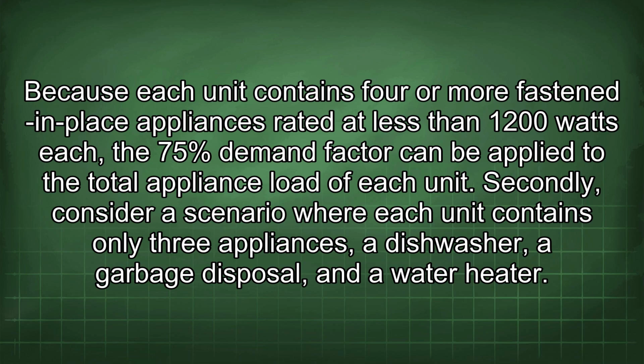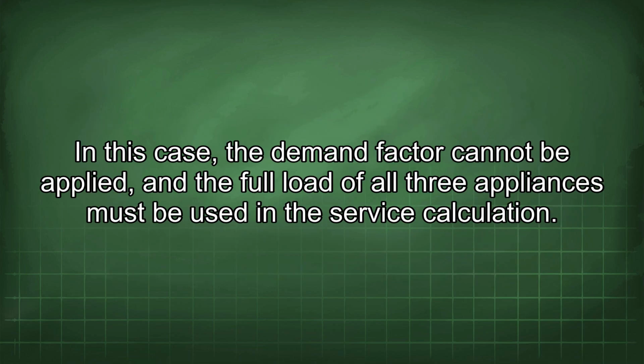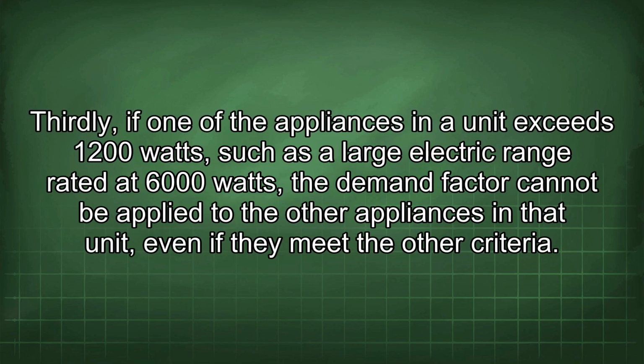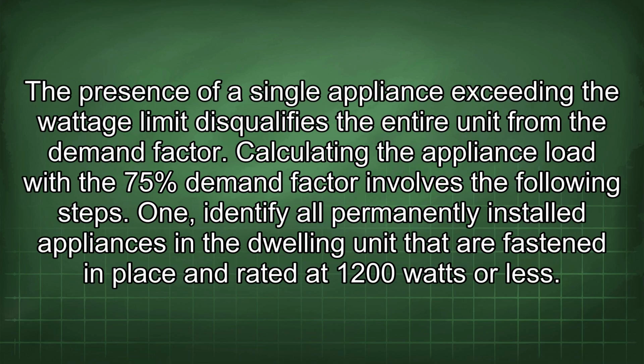Secondly, consider a scenario where each unit contains only 3 appliances, a dishwasher, a garbage disposal, and a water heater. In this case, the demand factor cannot be applied and the full load of all 3 appliances must be used in the service calculation. Thirdly, if one of the appliances in a unit exceeds 1200 watts, such as a large electric range rated at 6000 watts, the demand factor cannot be applied to the other appliances in the unit, even if they meet the other criteria. The presence of a single appliance exceeding the wattage limit disqualifies the entire unit from the demand factor.